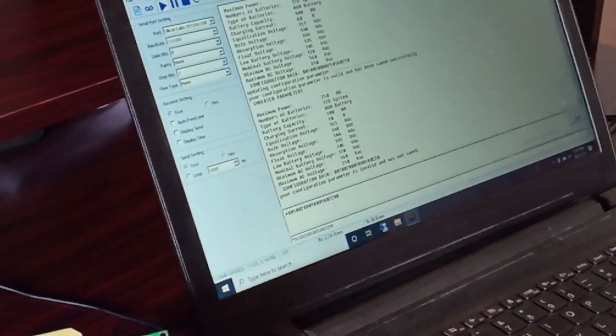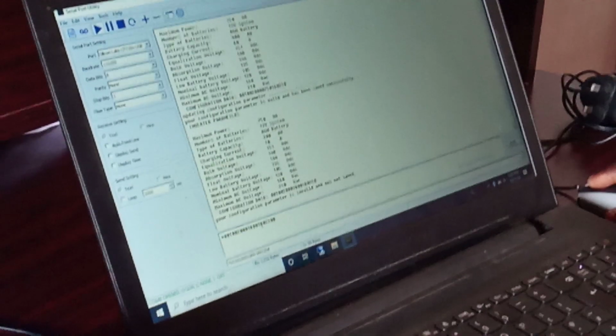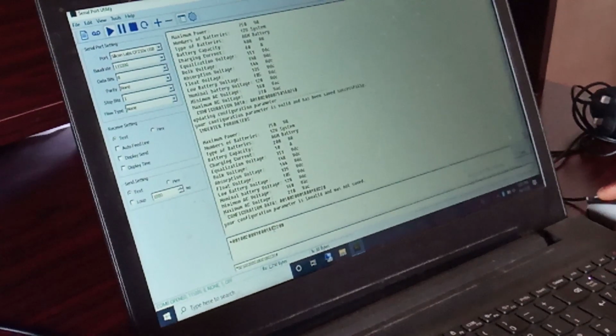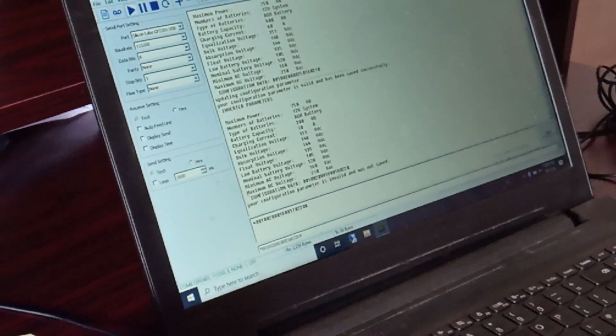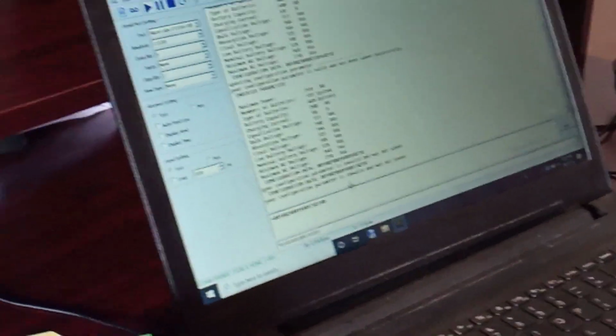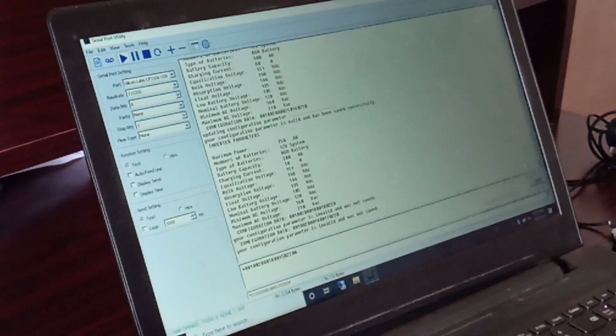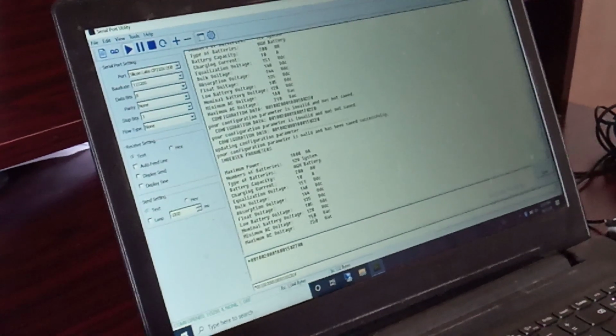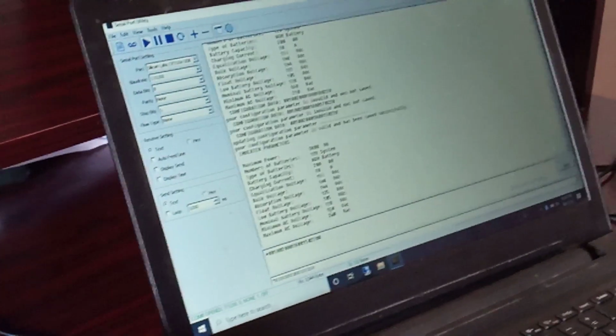So your configuration parameter is invalid and was not saved. That's because we actually set a value the minimum cannot be. The minimum threshold for the inverter cannot be greater than 180 because that's the lower range of the high threshold voltage. So what I can get maximum is 160. Let's try 170. I know 170 is not valid, so I expect to get an error, which we did. That is still an error. 170 is not a valid voltage for the minimum range. Let's say 150. Save. Okay, it took that. So like I said, it does not accept values for the minimum voltage outside 110 to 160, and for the maximum, outside 180 to 240.